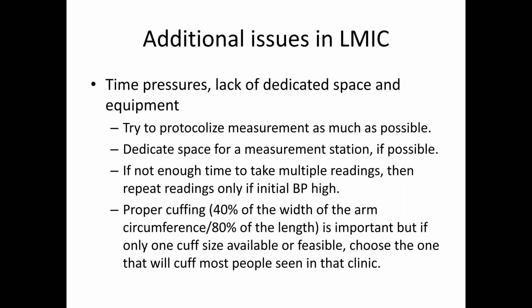The other thing is you may not have all the cuff sizes. And if you don't, then just choose the cuff size that fits most of the people that are seen in that clinic and go with that. And so you're going to undercuff. So if you're using too big a cuff, the blood pressure is going to be spuriously lower. And if you're using too small a cuff, the blood pressure is going to be spuriously elevated. But you do have to accept that if you have to compromise. Sometimes compromise is necessary. Next slide, please.